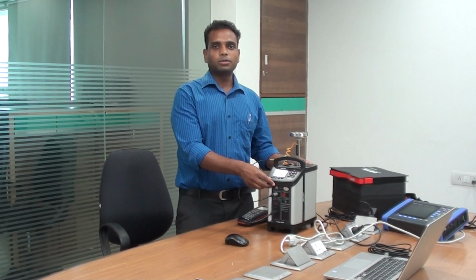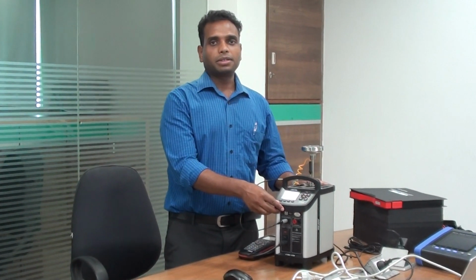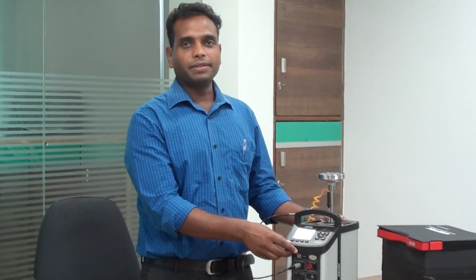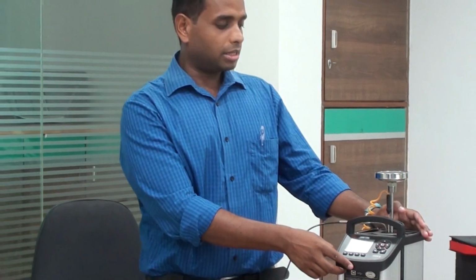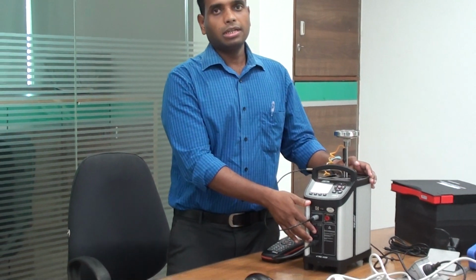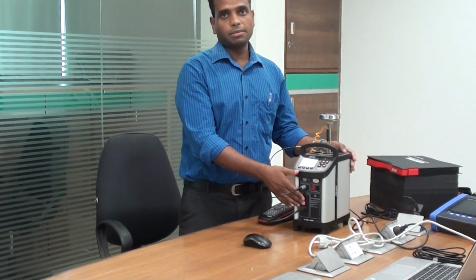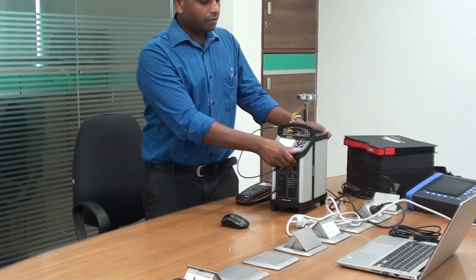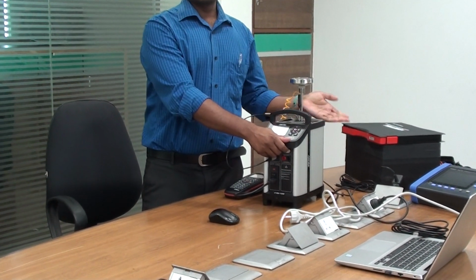Today I am going to demonstrate the Ametek temperature calibrator, Jofra CTC 155. The range is from -25 to 155. Accuracy of the instrument is 0.2 degree with the external reference sensor, and with the internal reference sensor it is 0.3. It is the very best model in the Jofra series, and we can consider it just a source because there are no inputs here. We cannot connect the DUT in the same instrument, and it is an upgraded version of the old CTC series.